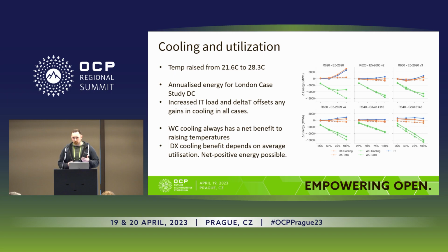Doesn't make sense for most of the direct cooling environments. Most of the direct cooling, where you're bringing air from outside, raising the temperature, the actual benefit you get from saving energy and raising the cooling is offset generally by the increased IT load and the cooling impact from the delta T. So your direct cooling, your air cooling system in London does not respond well to a raised temperature. It's basically a zero-sum game.